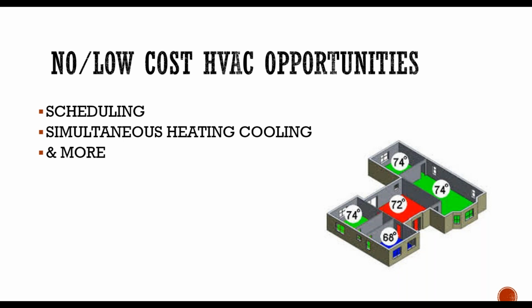I talked about simultaneous heating and cooling. I do want to talk about zoning. If you have the ability to zone, obviously it makes sense, right? Many times we'll go into a school or a church where just the pastor or the principal will come into his or her office and turn on the entire chiller just to condition that one room. So there's a number of ways around that. One option is, if you have the ability to zone, maximize the zoning as much as possible. If you don't, and you have one large chiller for your entire church, one thing to look at is adding an independent split system or air conditioning unit just over those offices.